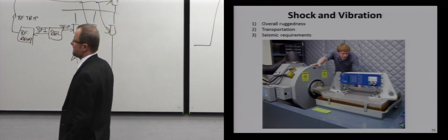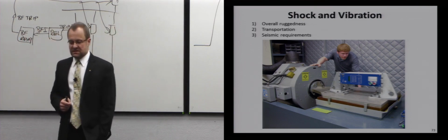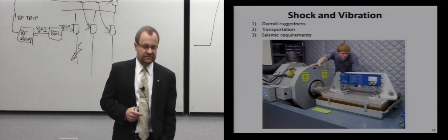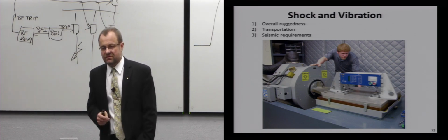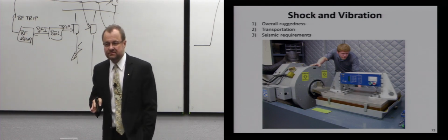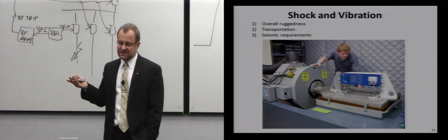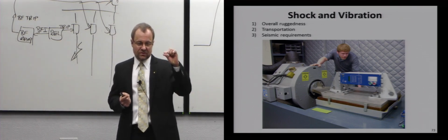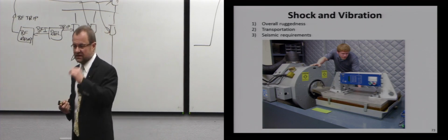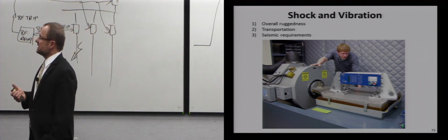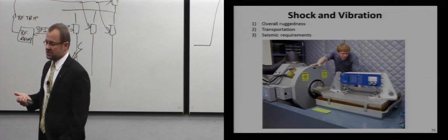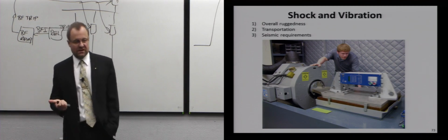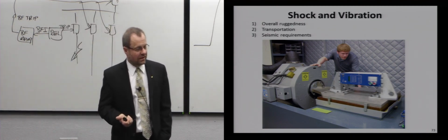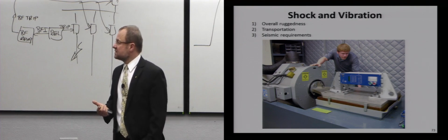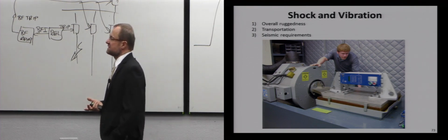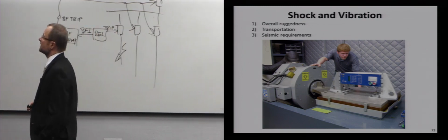Why do we do that? There are a couple of reasons. Some utilities have to follow seismic requirements, like in California, for example, where there is a real danger of earthquakes. That was a big problem for electromechanical relays because they do have moving parts. This thing doesn't have many moving parts. There is one, the output. You could get rid of it. You could put a thyristor instead of the clicker, and there are no moving parts. But that is also good for transportation, meaning that if you build the device properly, you know that it is not going to get destroyed on a FedEx truck. Handling, and it also checks the overall ruggedness of the design, that components aren't flying off the boards.